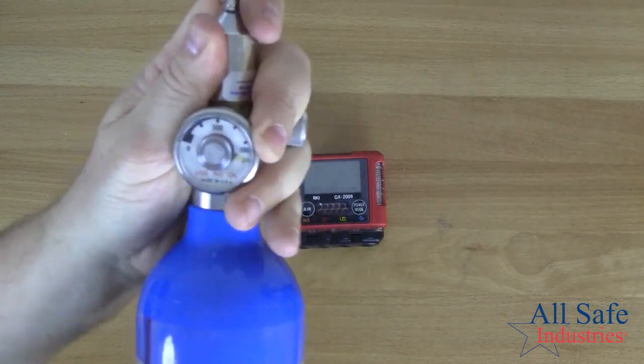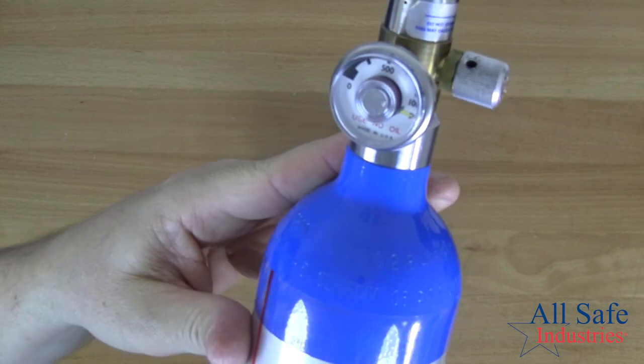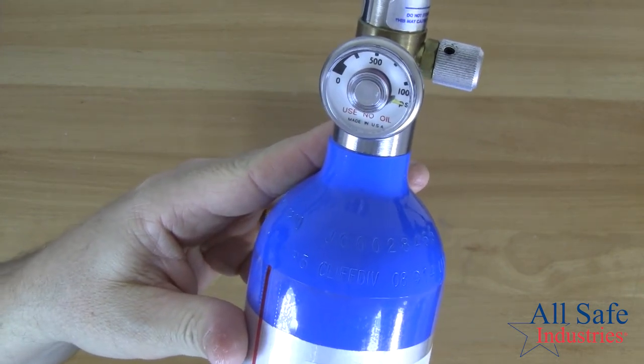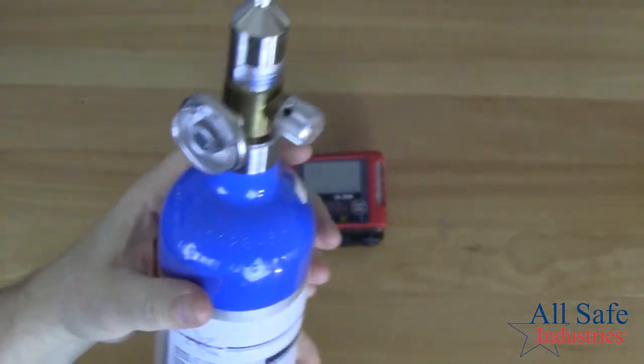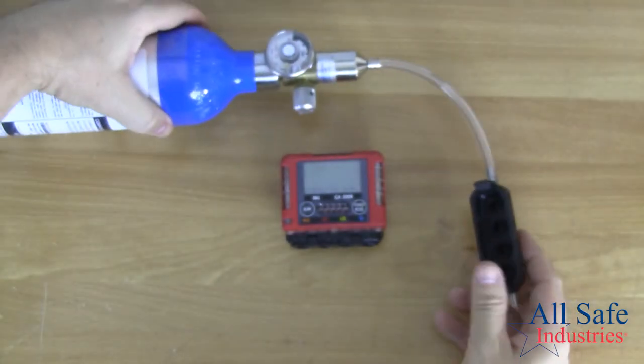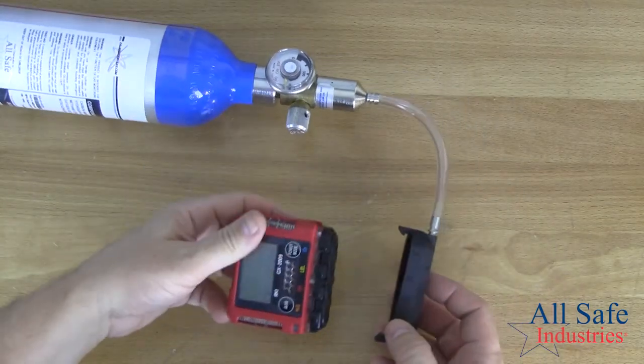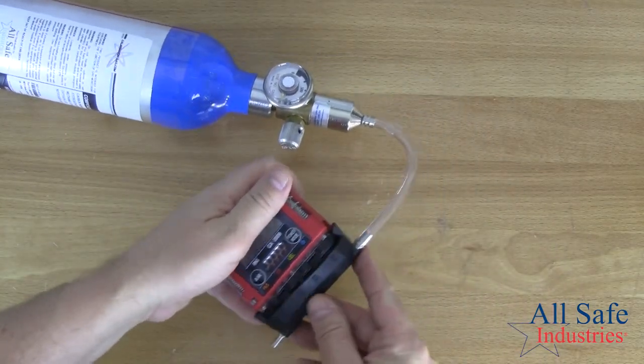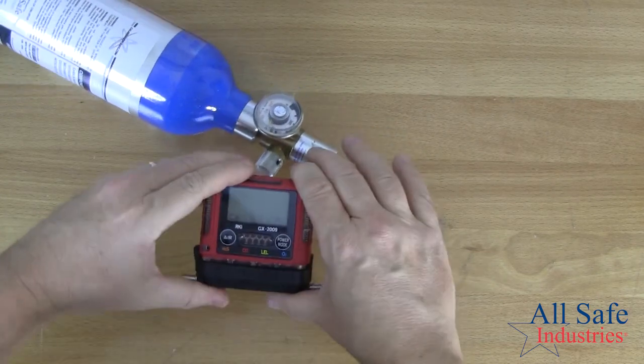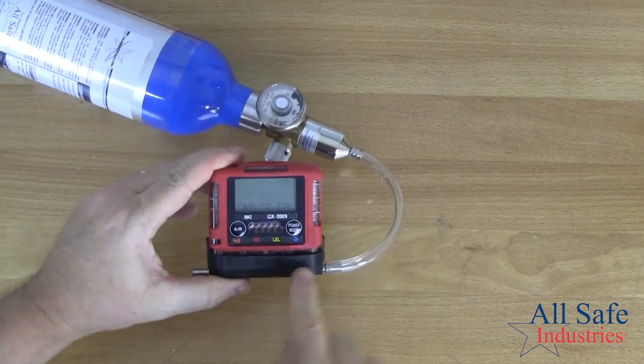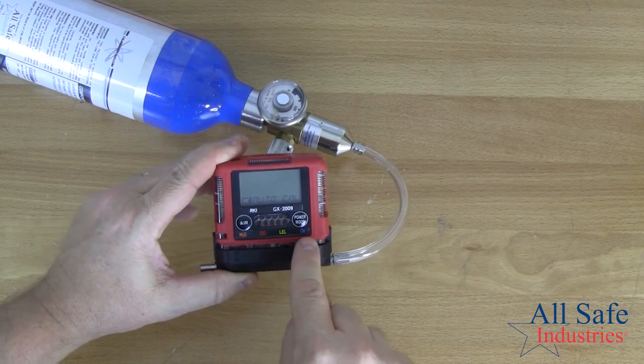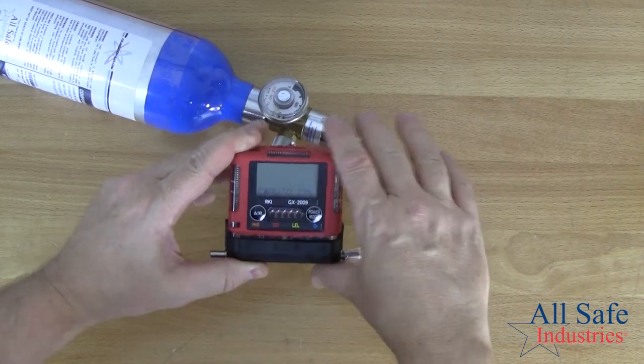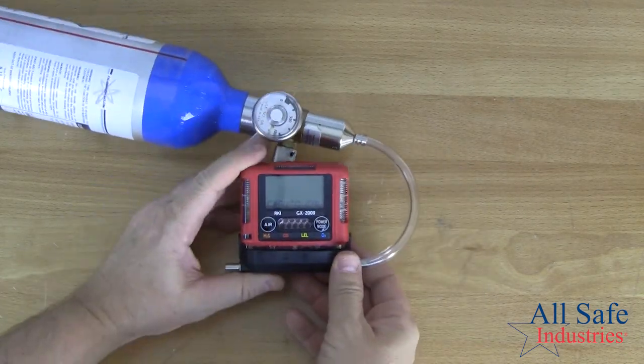You want to check the pressure valve to make sure that there is calibration gas in the cylinder, and I can see my needle says that I do. Then I can get my meter ready to accept the cal gas, so I'm going to go ahead and snap the cal cup on in the same way, matching up my sensor labels on the cal cup with the sensor labels on the instrument. And then I'm ready to enter the cal menu.